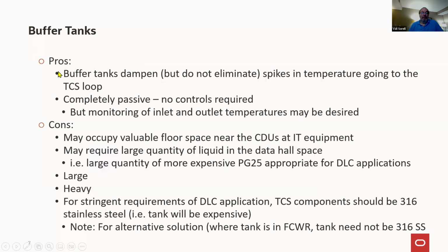So the obvious pros, like I said: it dampens the response, or the spike in the temperature that goes out to the technology cooling loop. It's completely passive. It just sits there. When normal conditions or low demand conditions return, it doesn't matter. It's like having a spring in the system. It absorbs energy, gives it back out. It just does it consistently, and no control is required. No bypass is really required. You may put a bypass just to clean it out occasionally if that's required, but usually the TCS loop water is very clean, so you could probably operate many years with it and not have any kind of concerns. But in essence, it just sits there passively doing its thing.